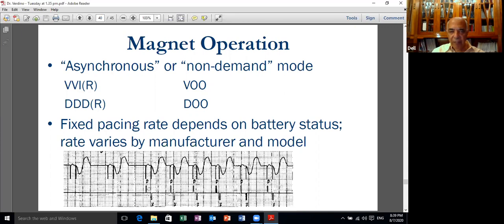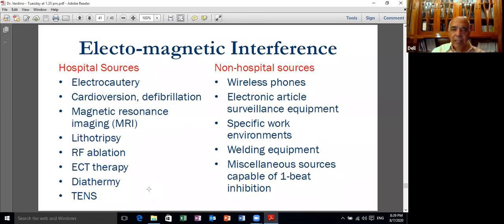And for every company and every specific pacemaker, there is a certain heart rate called the magnet rate, and it was used previously to indicate how much of the battery is left. Now, electromagnetic interference is an important subject. Actually, the hospital environment is the worst environment in which a patient can live with a pacemaker, because the hospital contains electrocautery, cardioversion, defibrillation, magnetic resonance imaging, lithotripsy, radio frequency ablation, ECT therapy, diathermy, and TENS, which is transcutaneous nerve stimulation. And outside the hospital, wireless telephones, electronic article surveillance equipment, if they are out of order. So under these circumstances, these conditions should be looked for.